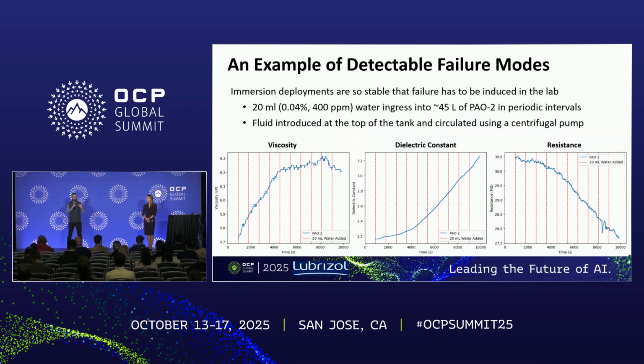Now, a more powerful message besides flat lines is when you can demonstrate when the line isn't flat. So if you can actually demonstrate failure, that you can show failure through data and monitoring, that says that we're behaving as expected, but we also know when things can go wrong. So we created a test in which we synthetically made things go wrong. So we set up a test in a similar test rig as to the presentation I gave last year, and introduced 400 ppm, so 4 times the amount that is typically in there from just saturation in the air.